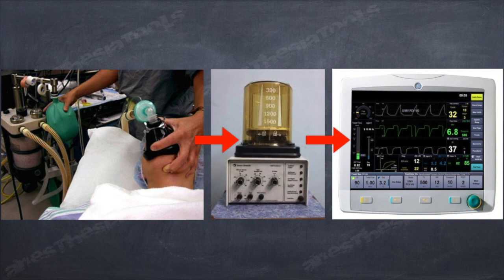The manner in which positive pressure ventilation is employed in anesthesia has undergone major changes. Ventilators that obtain the patient's minute ventilation from an anesthetic machine, delivered it to the patient, and then vented it into the atmosphere have been superseded mainly by devices that utilize circle systems and low flows.